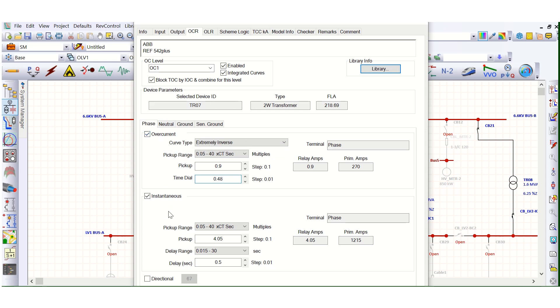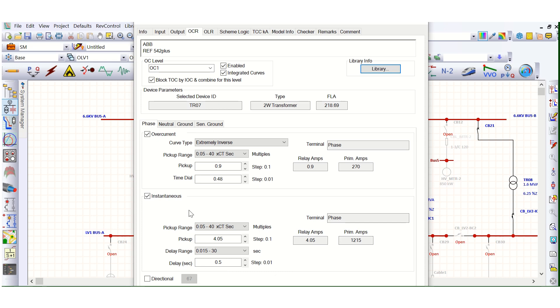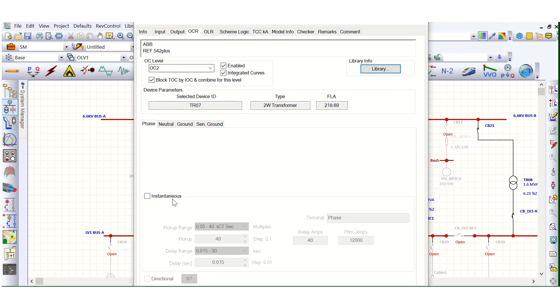Let's come back to this topic. So this 51, if I say this is Stage 1 and this is short time in 50 setting. This is 50 setting, but this is not actually instantaneous. This is short time setting. So if I call this Stage 2, then if we go here, this OC2 and if we enable here, there is no 51 in Stage 2, only instantaneous function is available.